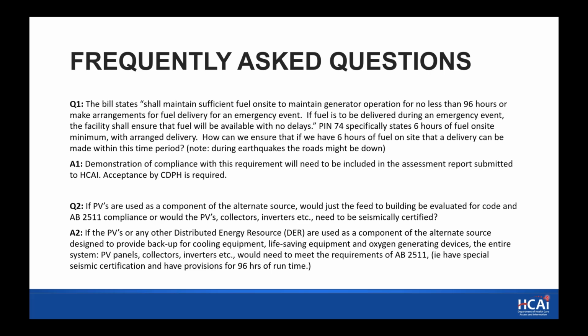So question number 1, the bill states, and this is in quotes, "shall maintain sufficient fuel on site to maintain generator operation for no less than 96 hours or make arrangements for fuel delivery for an emergency event. If fuel is to be delivered during an emergency event, the facility shall ensure that fuel will be available with no delays." PIN 74 specifically states 6 hours of fuel on site minimum with arranged delivery. How can we ensure that if we have 6 hours of fuel on site that a delivery can be made within this time period? Note, during earthquakes, the roads might be down. So I guess I would say if you don't think that you can ensure the fuel delivery, then I wouldn't pursue this option.